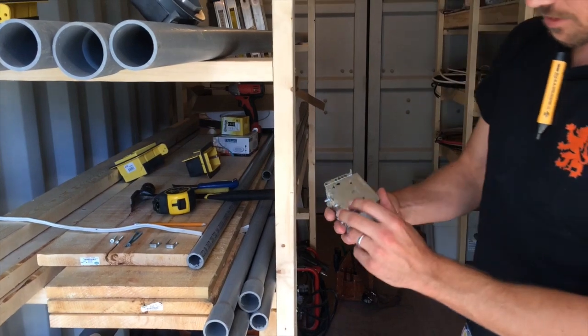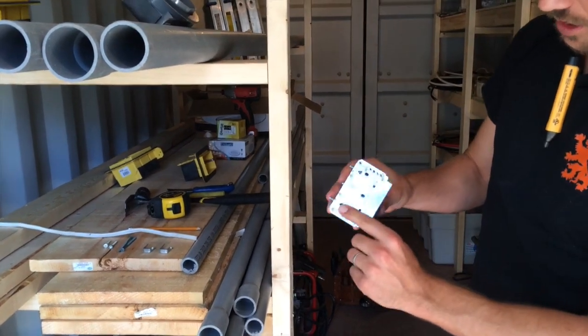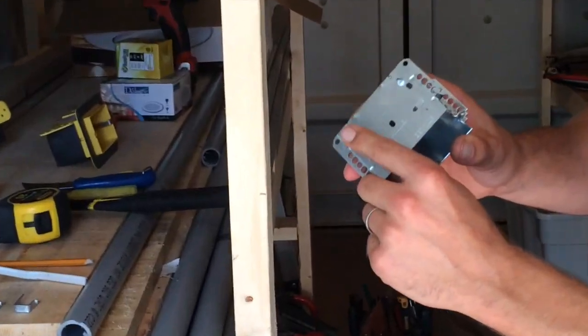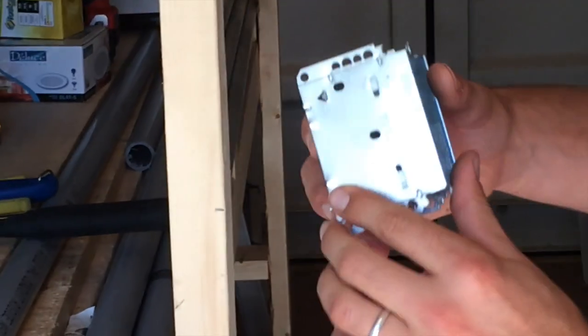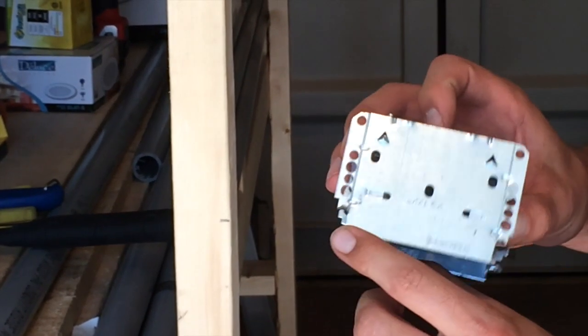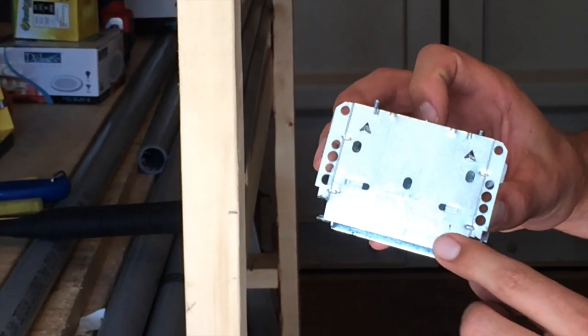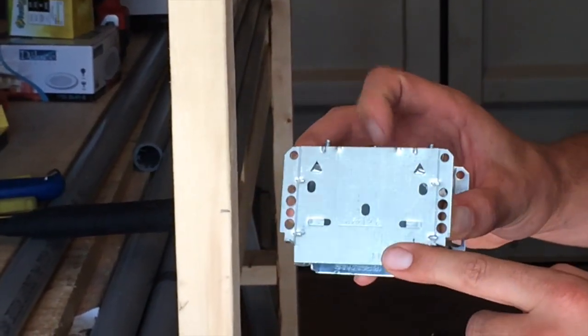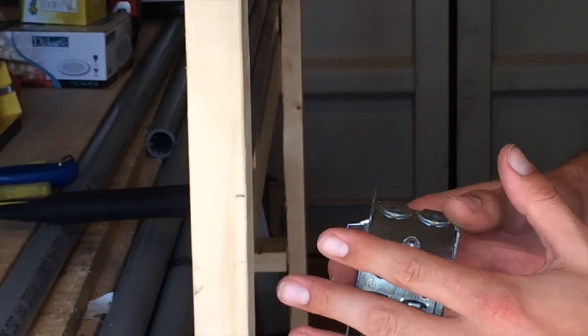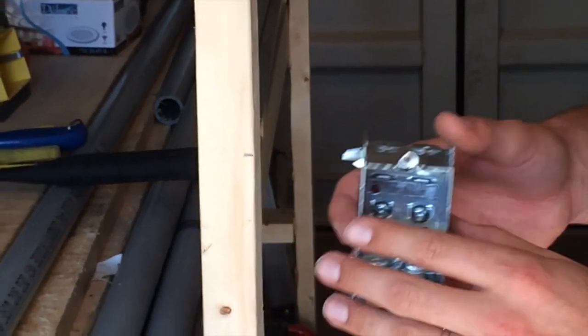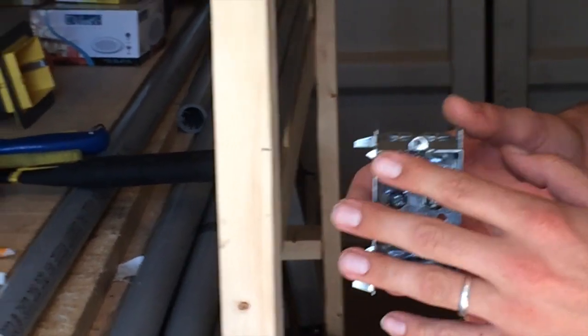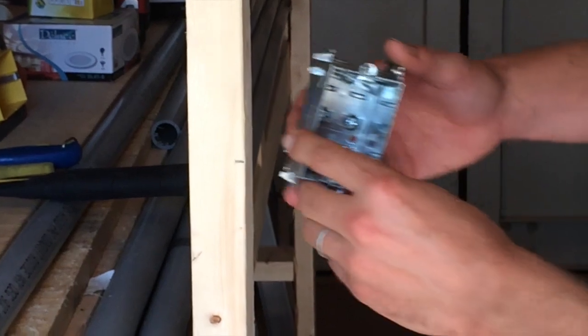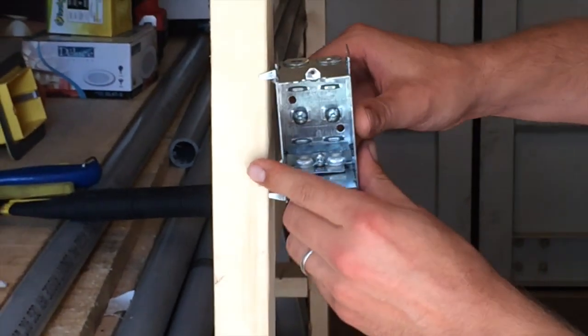These ones have a little push-in here, so you can see that they'll push into the stud, and then they have indicators for the drywall depth. So this is for a half-inch drywall, so it'll give you about an eighth of an inch recessed, which works out perfectly for a switch or a receptacle.